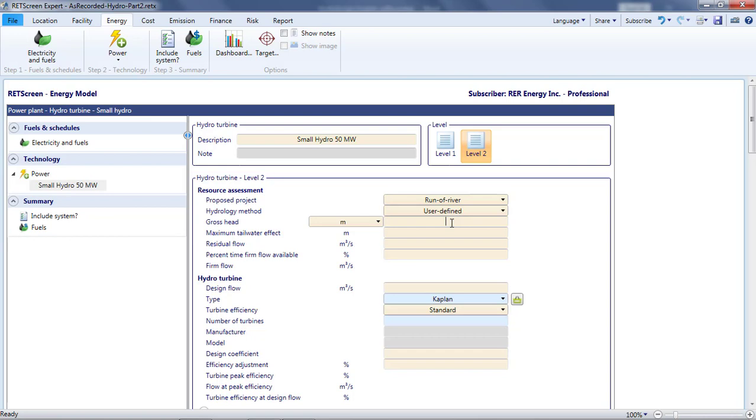The gross head is the change in elevation between the surface of the water at the project inlet, called the head water, and the surface of the tail water. The tail water is where water exits the project. It is called gross because head is a measure of pressure, and the gross head does not account for hydraulic losses, such as friction in the pipe, that reduce the pressure usable by the turbines to generate power. I've been told that the change in elevation on site is 80 meters, so I'll use this for the gross head.